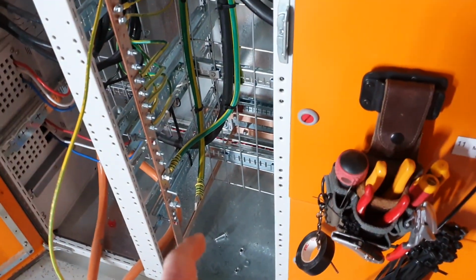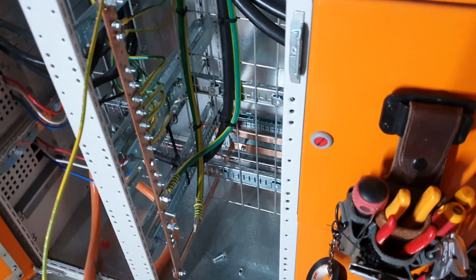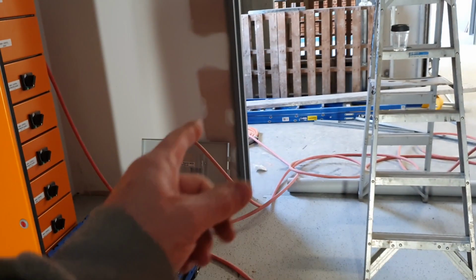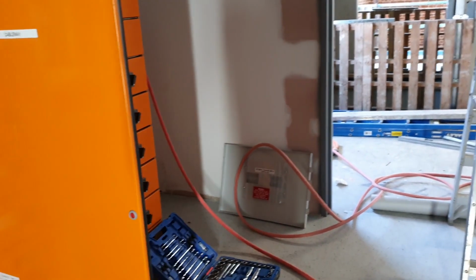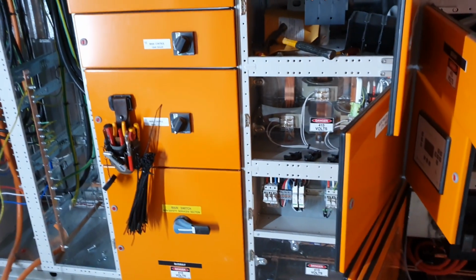We were getting a reading floating between 0.8 of a mega ohm and about 2. So what was happening - our main earth, which is here, we disconnected that. We've got the earth stake installed down in the pit, and the last little bit, over there where the driveway crosses, we've got some short underground conduit work. We thought the cable must have been damaged and sitting in the conduit, which typically fills up with water, and that was giving us our low reading.